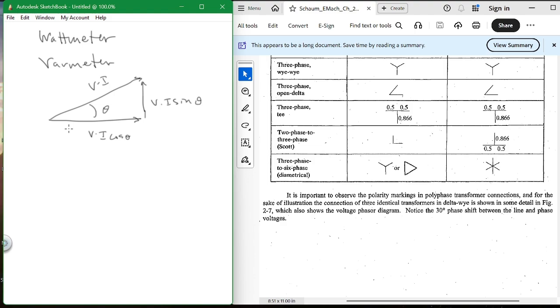If you oversize a motor - say a 25 horsepower motor on something that only requires 2 horsepower - what do you think happens to your power factor? What do you think happens to theta? It's really big - theta goes through the roof. If you size it for 25 horsepower and use it for 25 horsepower, theta is much smaller. But theta gets bigger if you undersize the load relative to the motor.